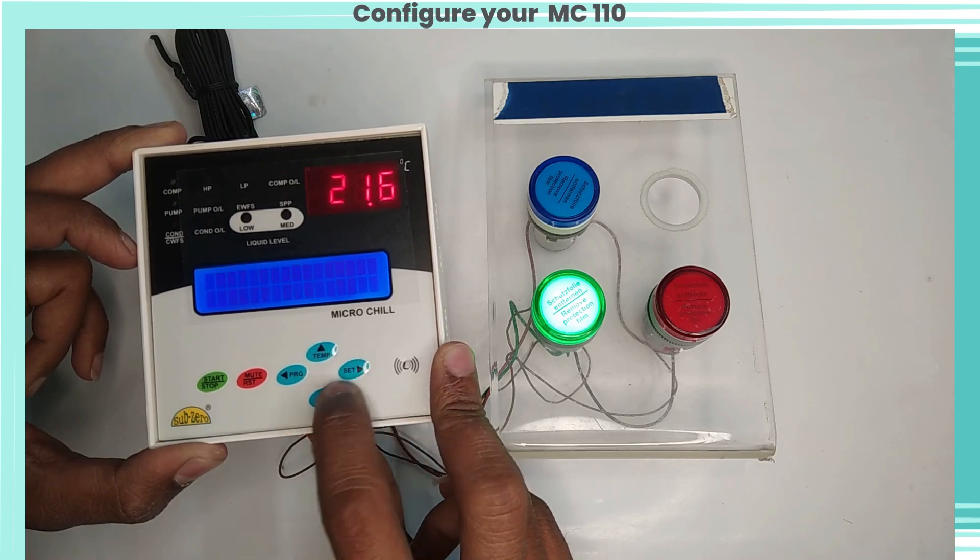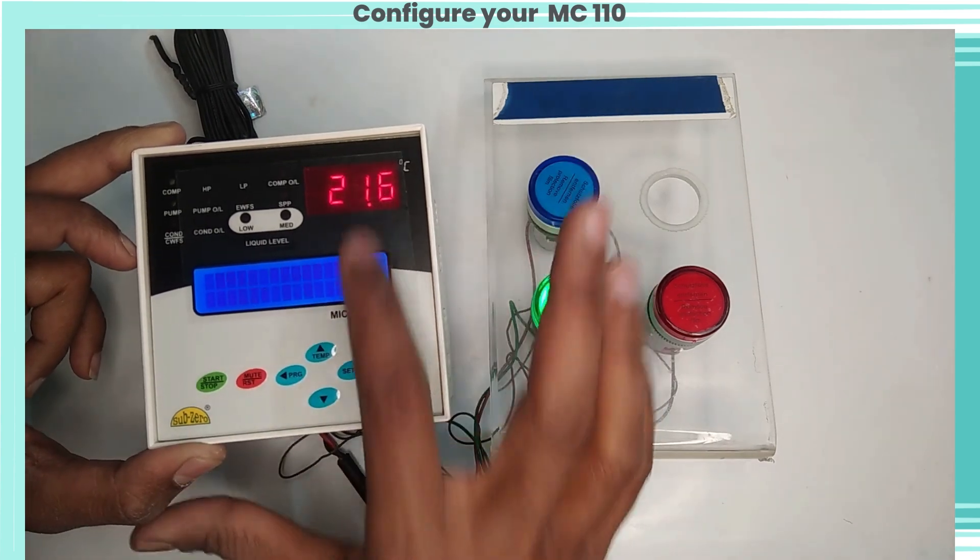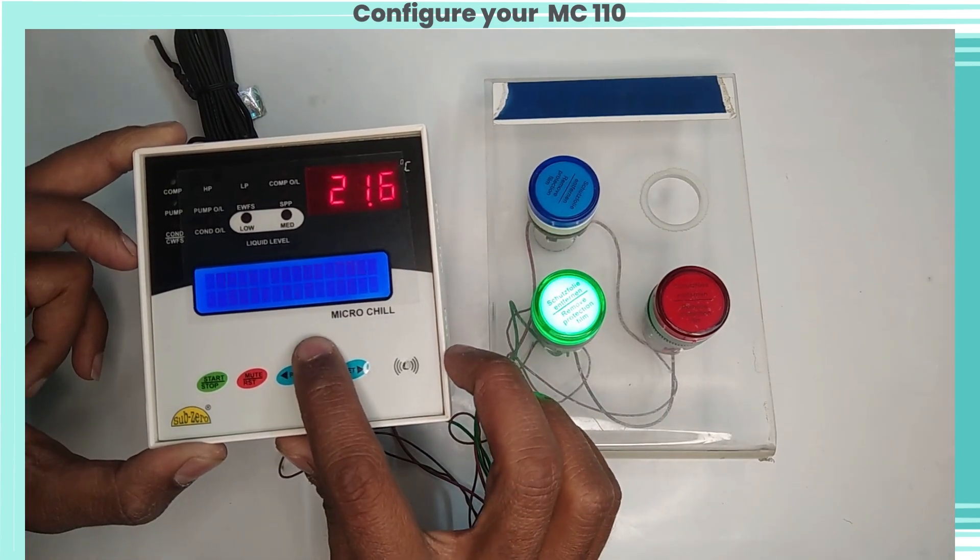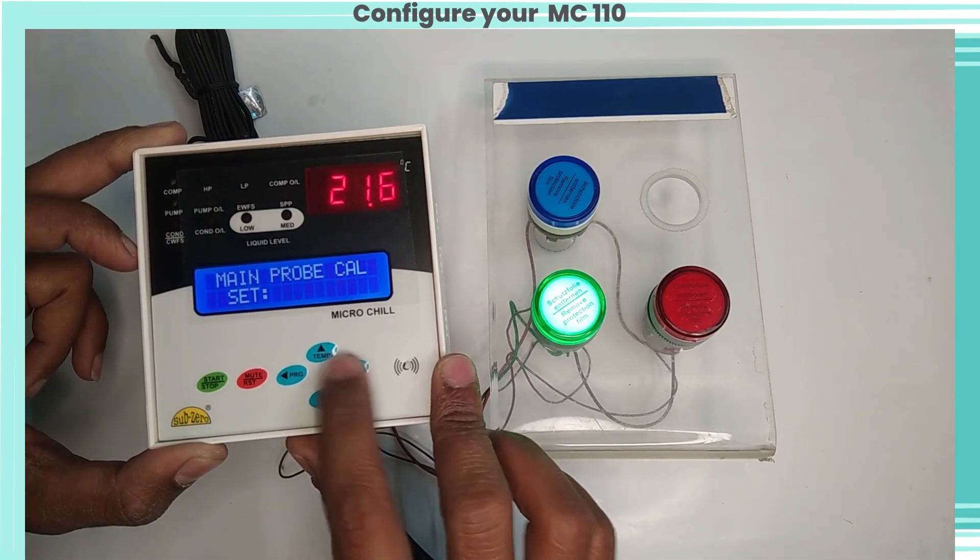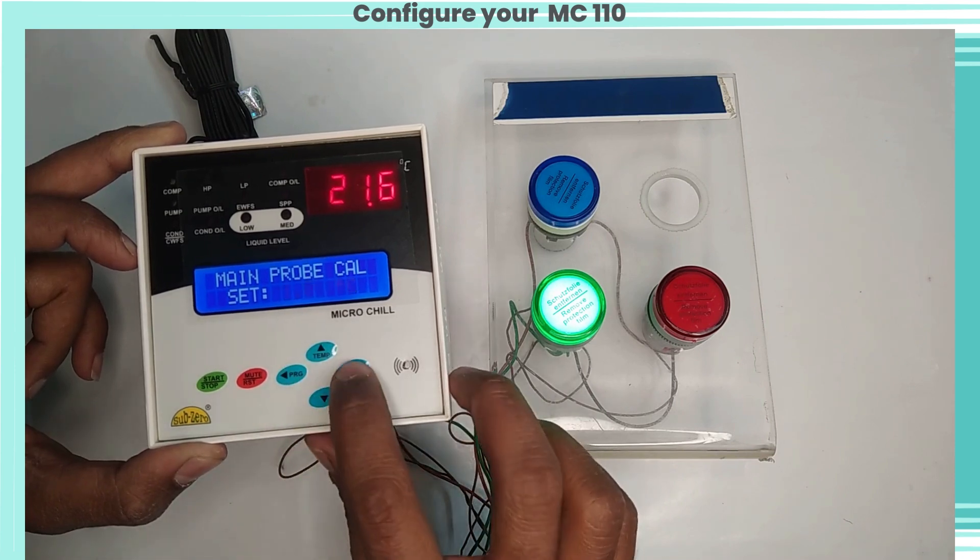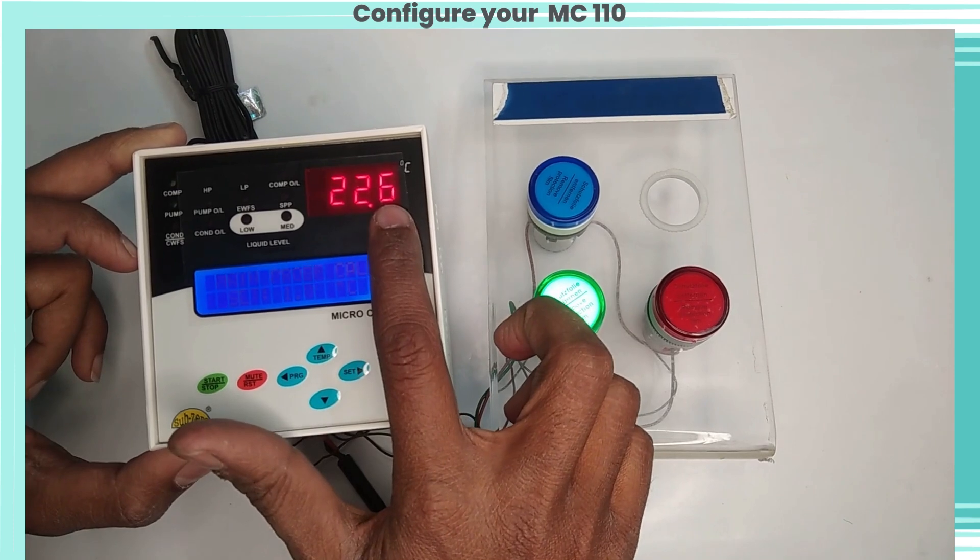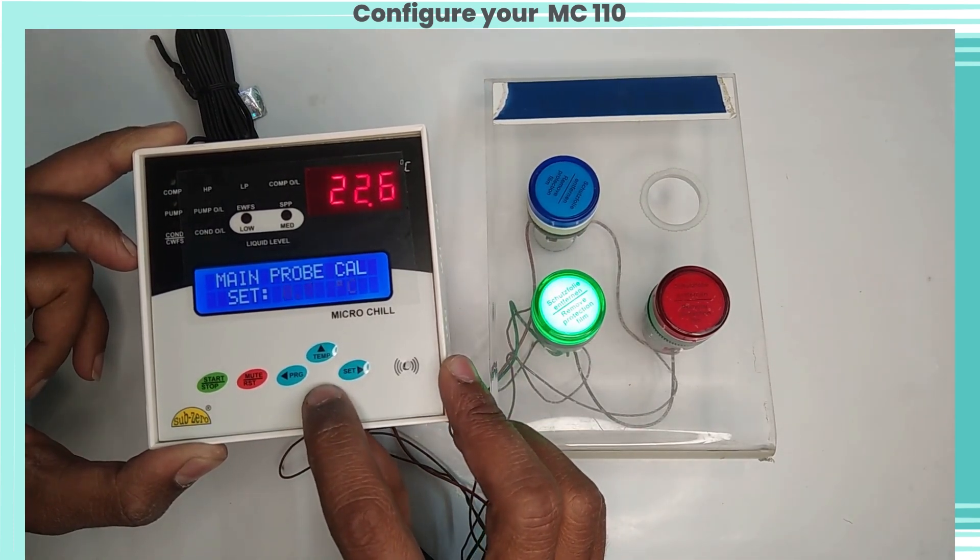For example, if the actual temperature is 20.0 degrees Celsius and the temperature on the controller shows 22.0 degrees Celsius, set this parameter to minus 2.0 degrees Celsius. And once out of this mode, the temperature will display 20.0 degrees Celsius.